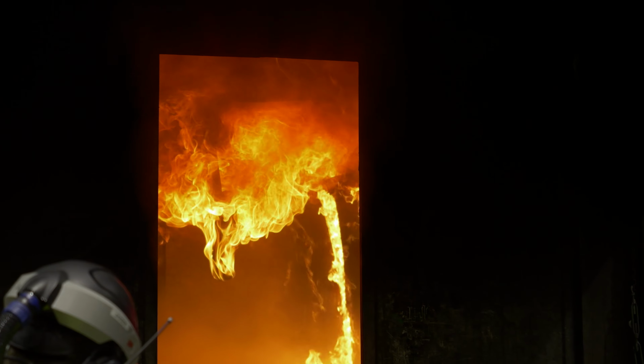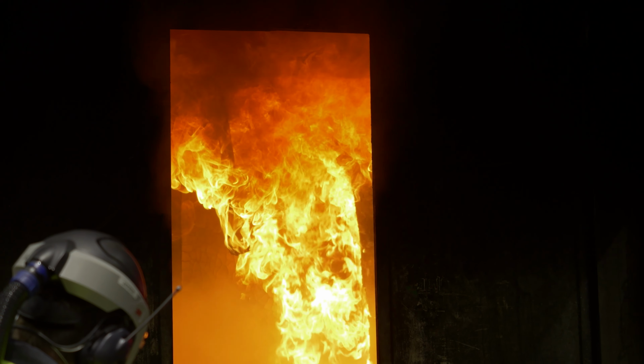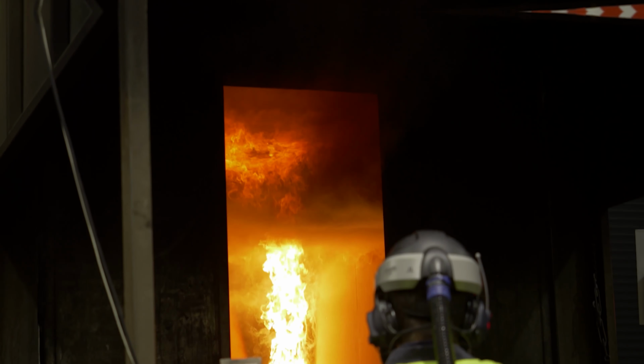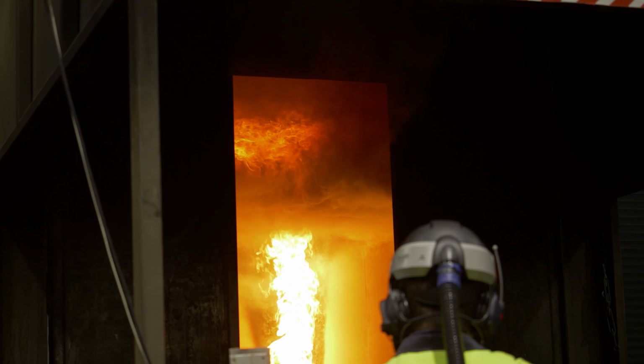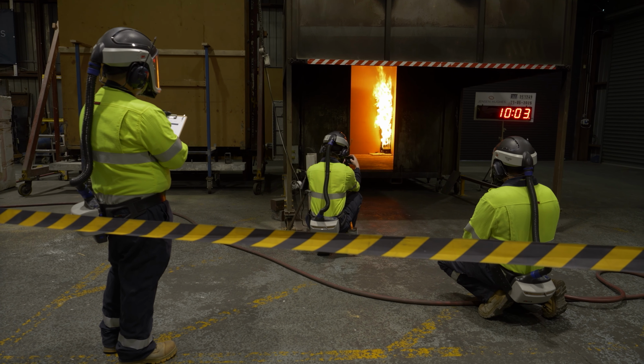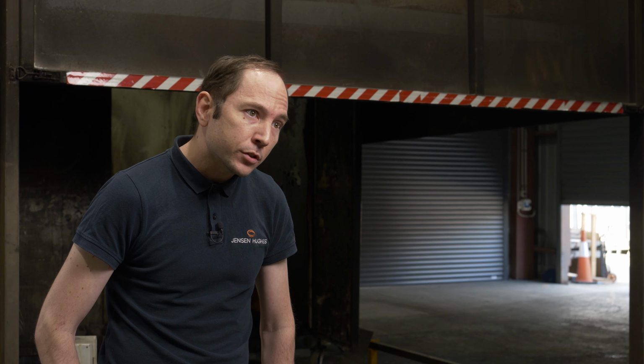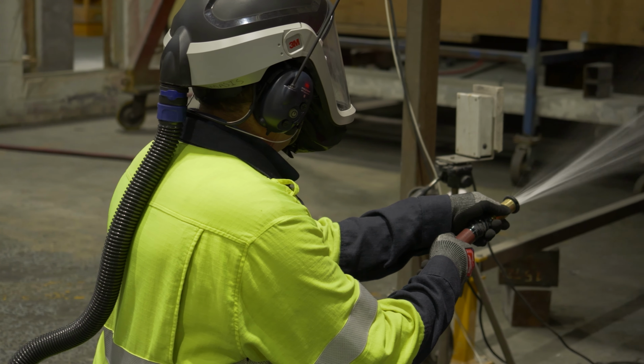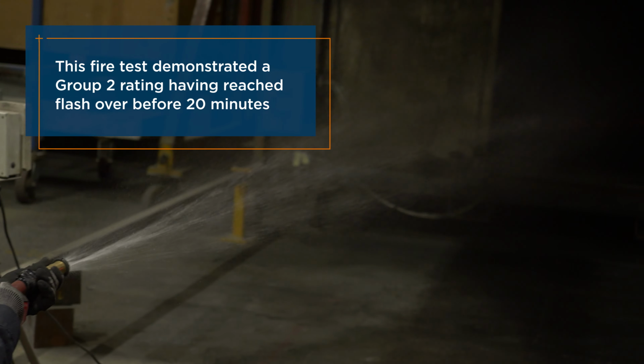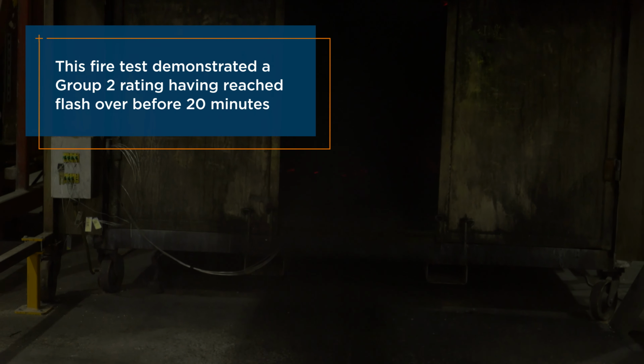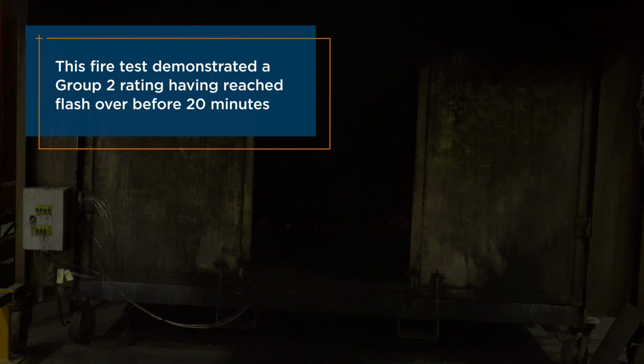While AS 5637 Part 1 allows for predictive group numbers based on small-scale cone testing, it is only where established correlations between small and large-scale performance exist. Materials that melt or shrink, have irregular surfaces, or assemblies in general tend to exhibit unrepresentatively better performance when evaluated in the cone. The test you just witnessed, for example, of a flame retardant impregnated MDF, demonstrated Group 2 performance in the room burn, having flashed over before 20 minutes, but results in a predictive Group 1 when evaluated on the cone calorimeter, indicating flashover would not occur.